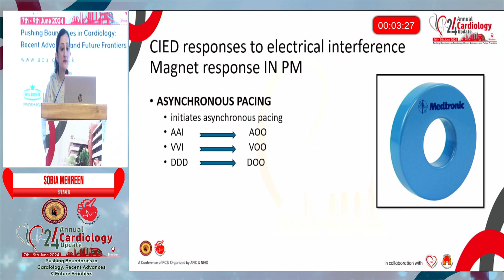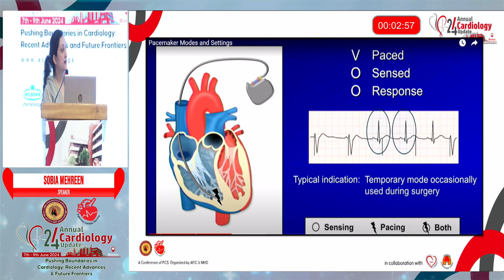Now, for example, if the patient is switched to VOO mode, the first letter represents the chamber paced, which is the ventricle. The second letter, the chamber sensed, is none. And the third letter, which represents the response to sensing, that is inhibition or tracking, is also absent. So there will be no response to sensing. The pacemaker will keep on pacing at a fixed rate regardless of the patient's intrinsic QRS complexes.